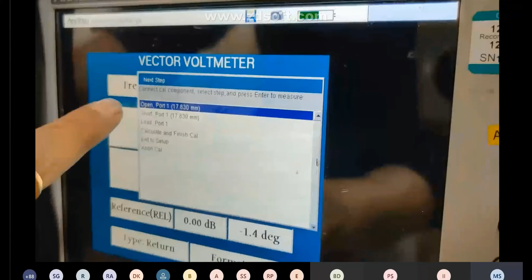Now we'll start with calibration. This window will pop up, and you have to follow the steps. The steps say: connect cal component, select step, press enter. So you have to connect the open port to port number 1.